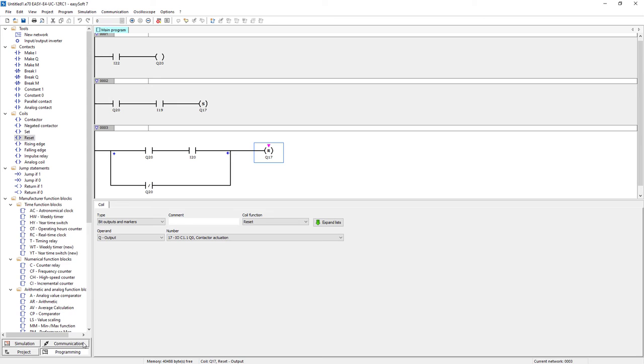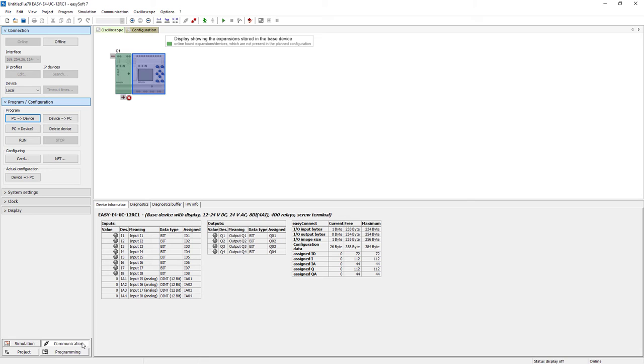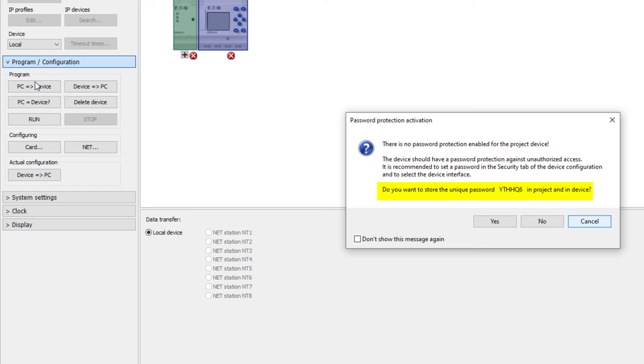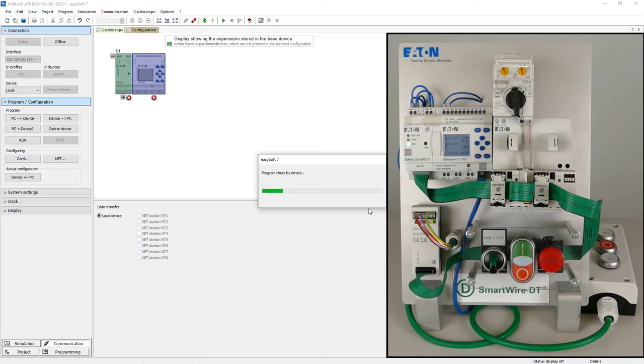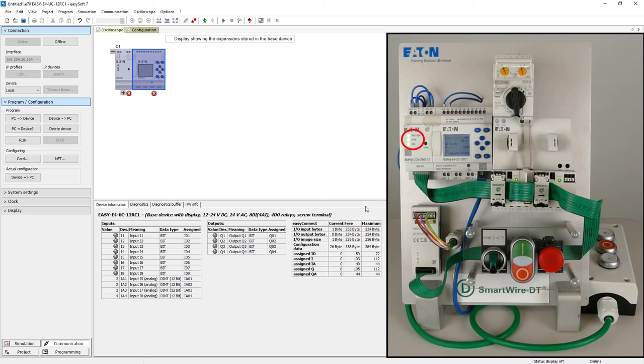Via communication and the button PC to device the download of the created program is initiated. When the transfer is started a security query is displayed for cyber security reasons since no password has been set in the project setting. In this example no password is used. Once the SmartWire configuration has been successfully downloaded the SWD and config LEDs will go to steady light.